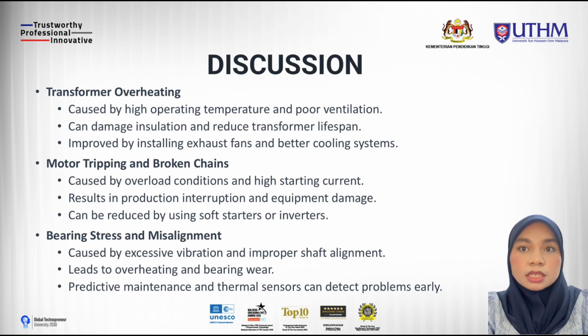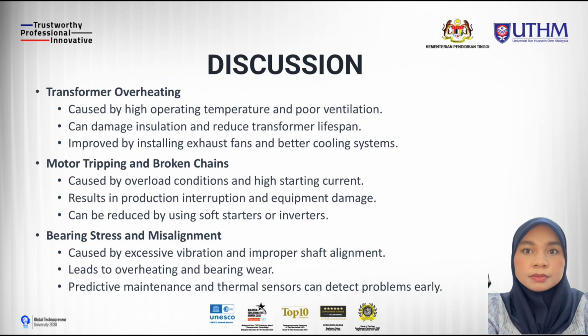The second is motor tripping and broken chains due to overload conditions and high starting current. This problem can interrupt production and damage equipment. The use of a soft starter and inverter can help reduce this issue by controlling the starting current.